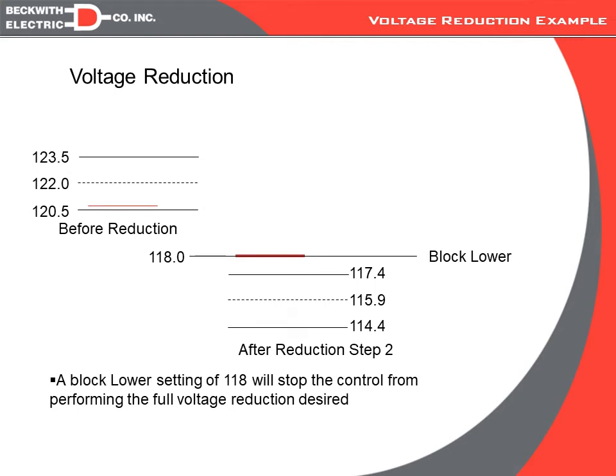One last thing to remember on voltage reduction is the block lower setting, as we talked about in the blocking session, will block voltage reduction. So if we set our block lower at 118, but we want after voltage reduction to be down around 116, that's not going to happen. So a lot of utilities misset the block lower by looking at the lowest voltage they would normally want to have on a circuit instead of what the lowest voltage they want in an emergency condition after going into reduction.